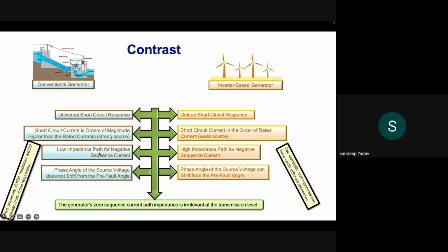When it comes to feeding negative sequence current, whenever there is an asymmetrical fault, a line-to-ground fault or a double line-to-ground fault, the conventional generators can feed large negative sequence currents, and these are very important when it comes to protective relaying of transmission lines and other components in the system. However, in case of IBR, because they are current limited, first of all, and second, by virtue of their grounding and the rating of the DC link capacitor, the negative sequence current is usually limited by the controller, because it cannot feed negative sequence current for a sustained period of time. That would require a very large DC link capacitor, which is against the very economics of inverter-based resources.